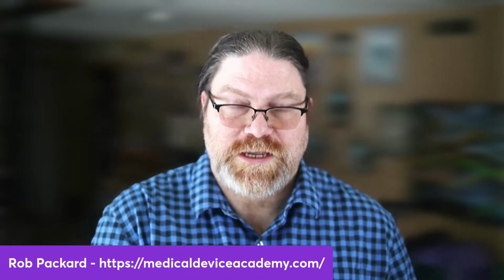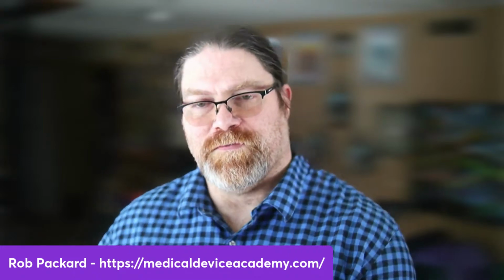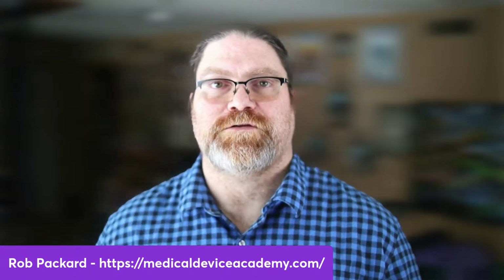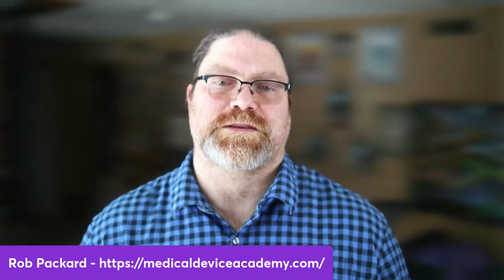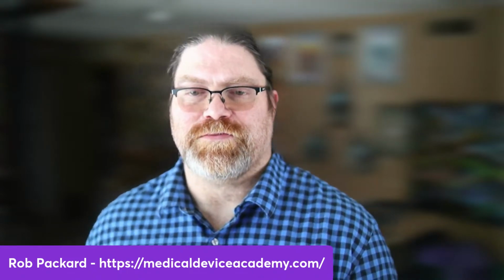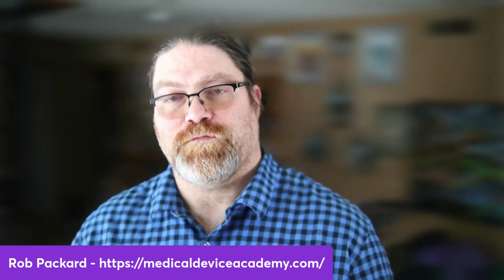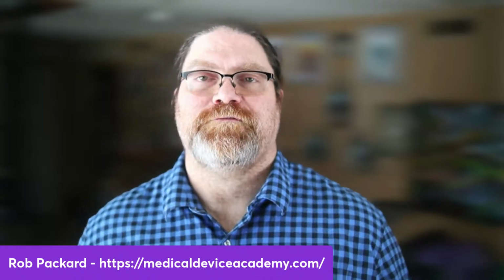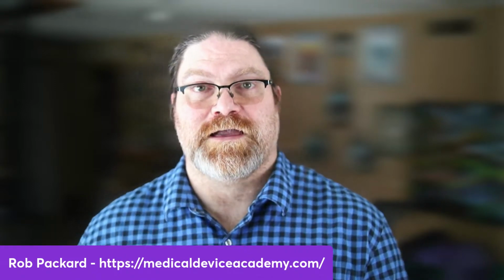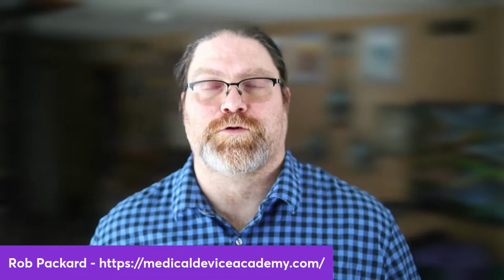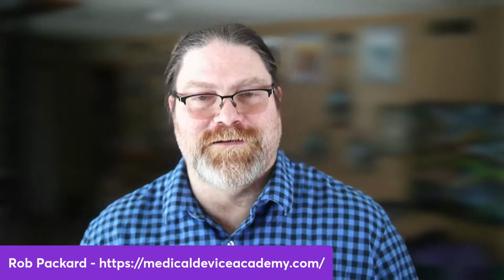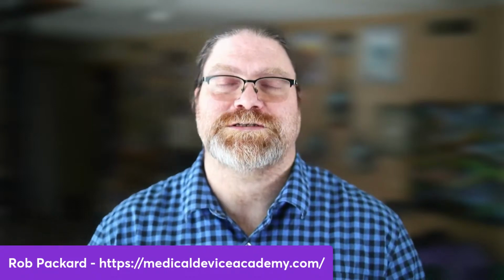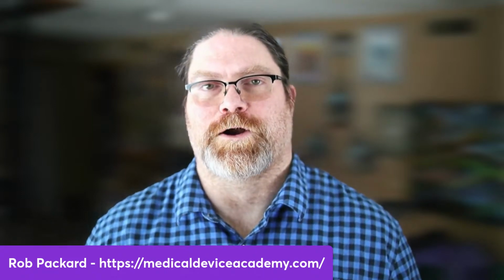So make sure that you do it in order. Procedure first, then those 4 documents, then get some feedback. Look for a vendor that knows 62304, knows how to do a risk analysis for software, and then hire them, and then we can start into reviewing documents. And if you've already got something that's working, think of that as a proof of concept. That's not a finished product. And I know you wanted to go to market with a proof of concept, but the FDA says no, because you have to follow these standards. So you have a proof of concept. Congratulations. Now let's help you make that something we can get on the market.